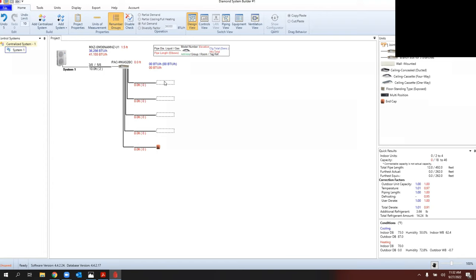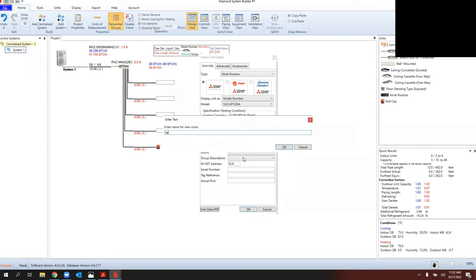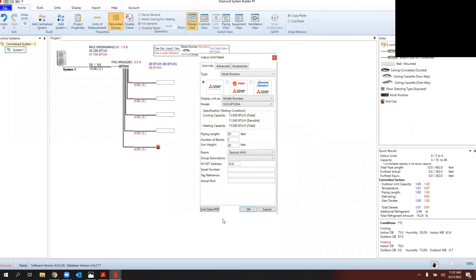The SM36 and 4C36 have a maximum of four connections, not five. If you try to connect five, it throws an error. So I like to put an end cap on the fifth port right away. Also, the MKA52 branch box has a larger connection on the first port than the rest, so I highly recommend putting the largest capacity indoor unit on Port 1 to minimize the chance of needing port adapters. I'll connect a ducted unit — an SVZ air handler one-ton unit going into an attic, 30 feet of pipe, 20 feet up.